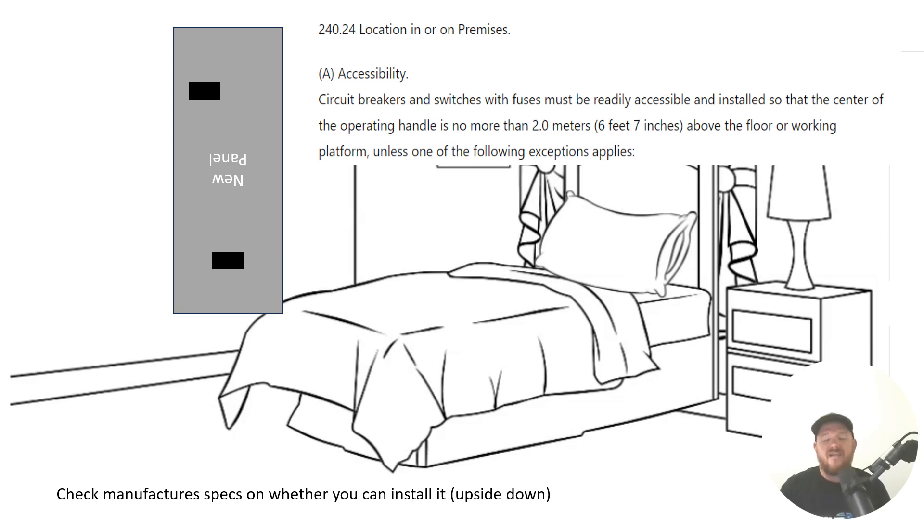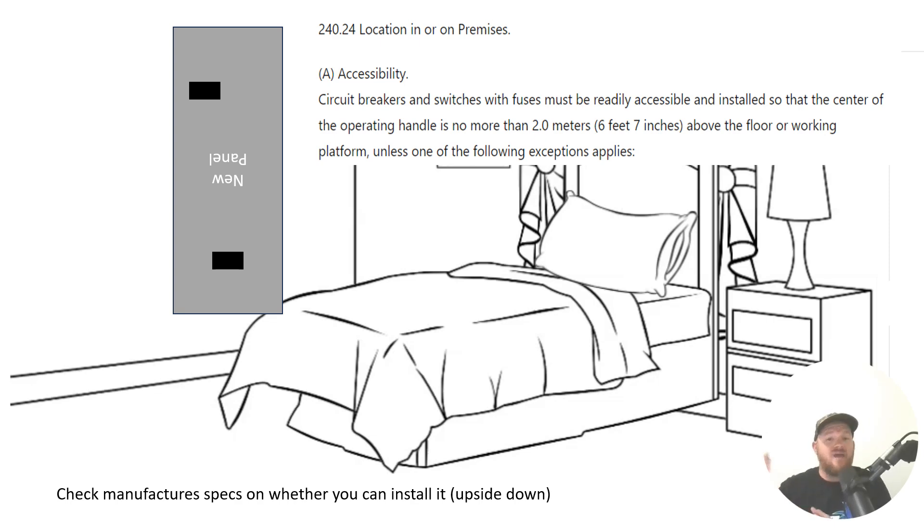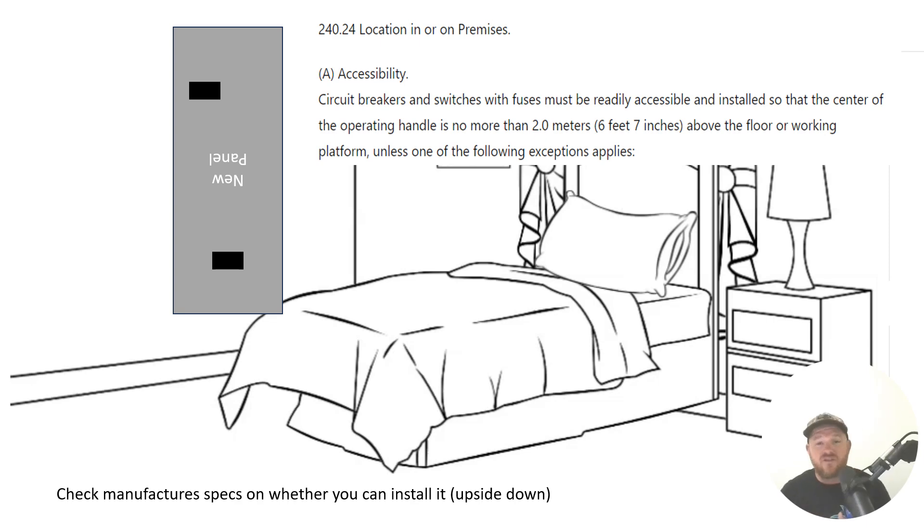As long as the breaker that's feeding that branch circuit is lower than six foot seven and accessible, then it's okay because you can turn it off at a readily accessible location. Then up there, if you want to have another breaker or fuse, that's likely going to be okay. That's one of the scenarios where you are allowed to do it.